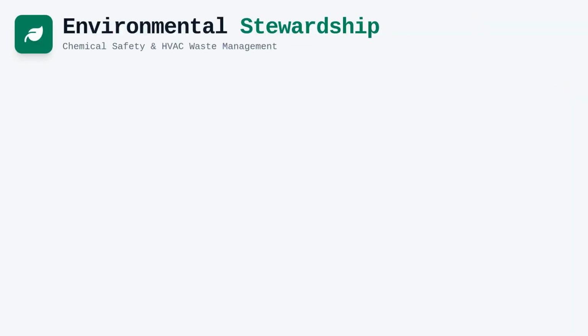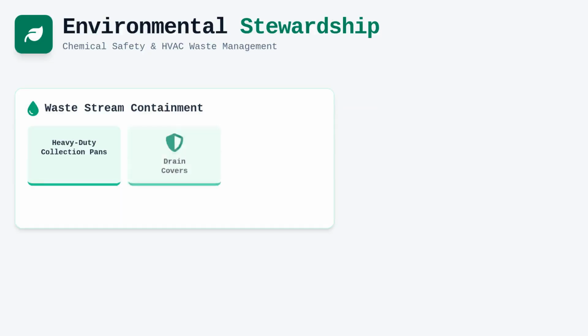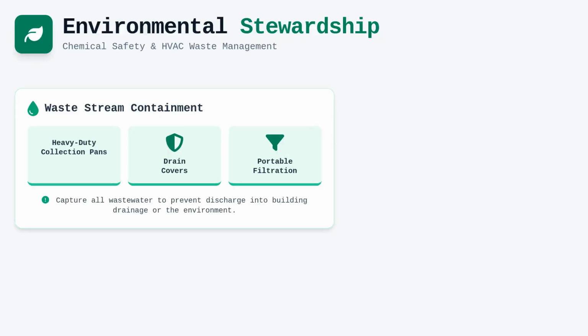Environmental stewardship remains a critical responsibility when using chemicals in an operating HVAC system. You must capture all wastewater and chemical runoff to prevent the discharge of contaminants into the building's drainage system or the environment. This necessitates the use of heavy-duty collection pans, drain covers, and, if necessary, portable filtration or reclamation units to manage the liquid waste stream.